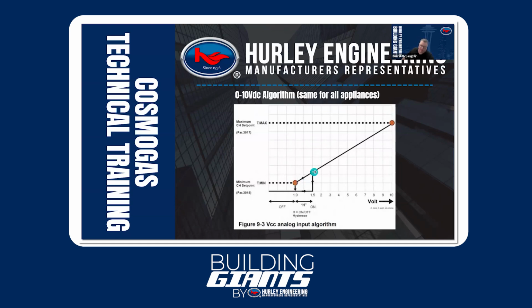Now, a lot of boilers are required to have two different signals. They'll need a modulation or a signal to change the set point, an analog signal for that. And they'll also need a binary signal, an on and off, just to tell it to turn on and off. CosmoGas does all that with one signal. So the 0 to 10 signal operates between 1 and 10 for set point. But if I drop that signal below 1, that's the signal to tell the boiler to just turn off.